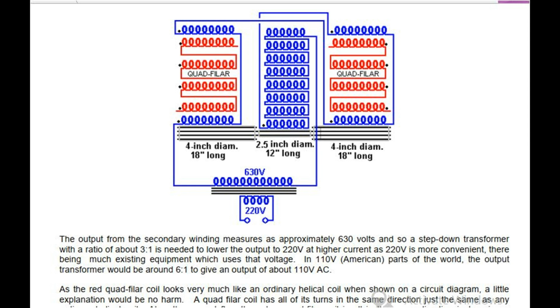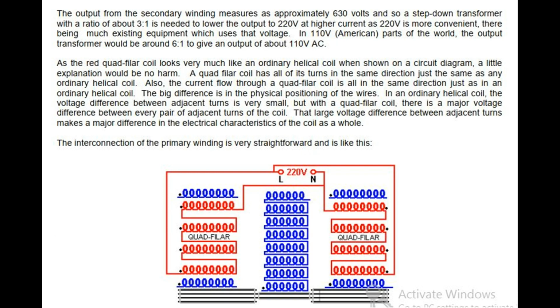A quadfilar coil has all of its turns in the same direction, just the same as any ordinary helical coil. Also, the current flow through a quadfilar coil is all in the same direction, just as in an ordinary helical coil. The big difference is in the physical positioning of the wires. In an ordinary helical coil, the voltage difference between adjacent turns is very small, but with a quadfilar coil, there is a major voltage difference between every pair of adjacent turns of the coil. That large voltage difference between adjacent turns makes a major difference in the electrical characteristics of the coil as a whole. The interconnection of the primary winding is very straightforward and is like this.